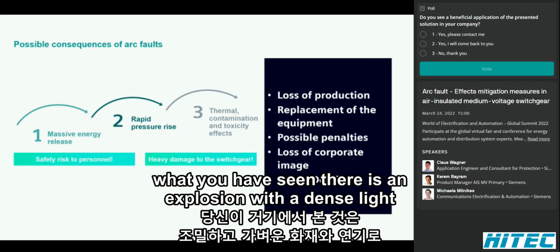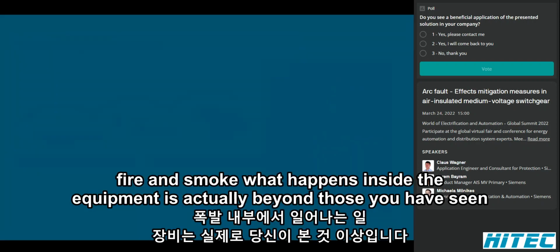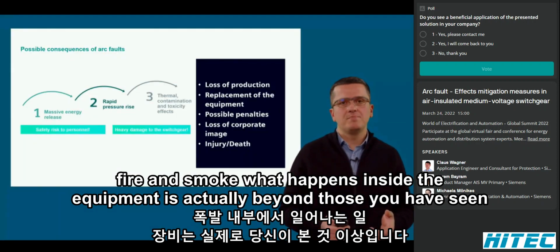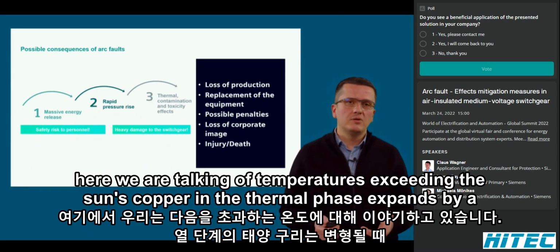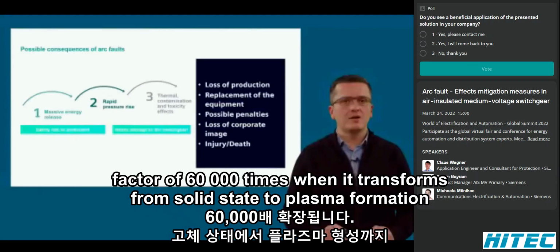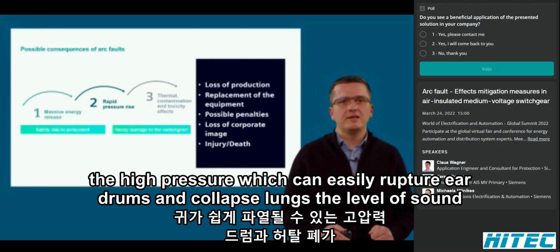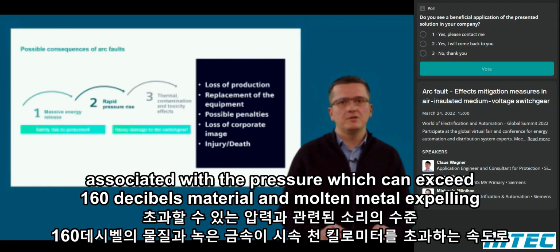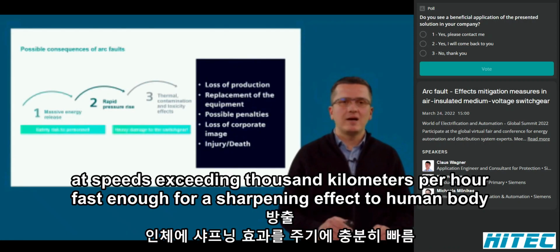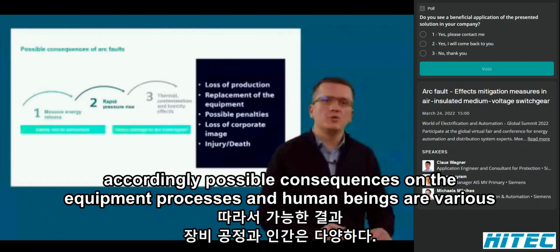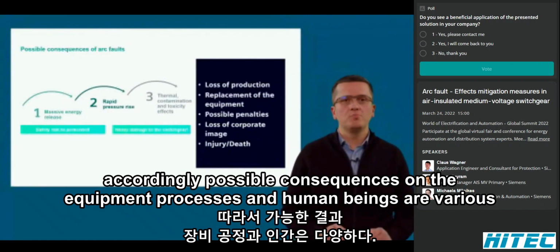What you have seen there is an explosion with a dense light, fire, and smoke. What happens inside the equipment is actually beyond those you have seen. Here we are talking of temperatures exceeding the sun's. Copper in the thermal phase expands by a factor of 60,000 times when it transforms from solid state to plasma formation. The high pressure, which can easily rupture eardrums and collapse lungs. The level of sound associated with the pressure, which can exceed 160 decibels. Material and molten metal expelling at speeds exceeding 1,000 km per hour, fast enough for a shrapnel effect to human body. Accordingly, possible consequences on the equipment, processes, and human beings are various.